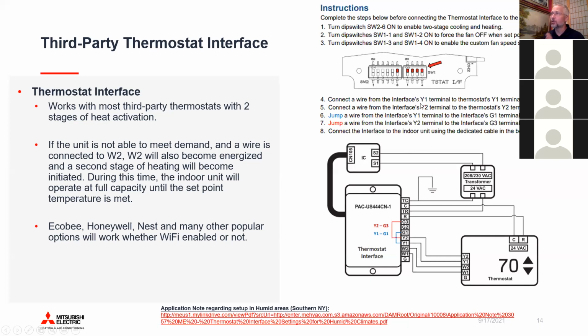And what I've highlighted here on this slide are recommendations for setting the system up in areas where there's a high latent load, high moisture content, high humidity, like Southern New York. There's an app note related to this, and I've put the link down here at the bottom. You can find it on my favorite website, www.mylinkdrive.com. In the app notes section under controls, there's a note specifically about using the third-party thermostat in high latent areas. And frankly, this diagram and similar instructions on how to configure it are all laid out in the exhaustively well-detailed installation manual for the third-party thermostat.